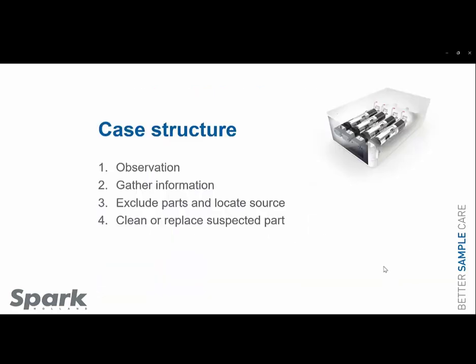We will continue with the cases. Each case is based on a certain structure. First, we will check the observations the end user and the engineer made. Then we will collect information from maintenance mode, service mode, the pressure graph and the advanced pressure view. After that, we will exclude parts which are probably not related to the source of the issue. Then we will start to clean the pump or even replace suspected parts.